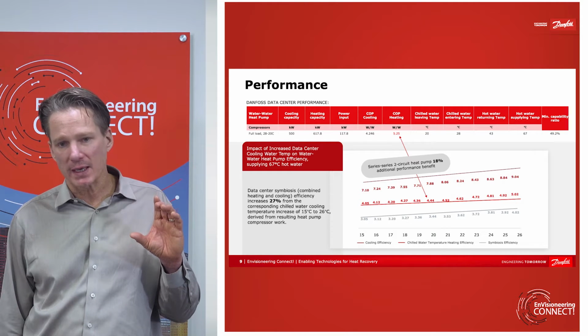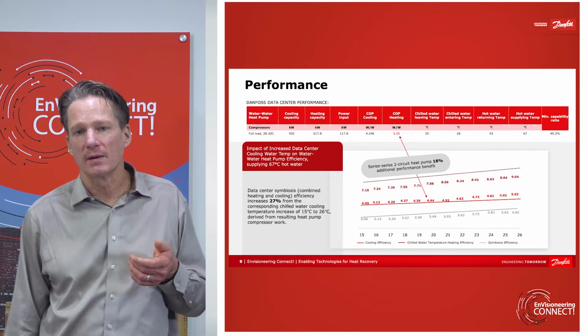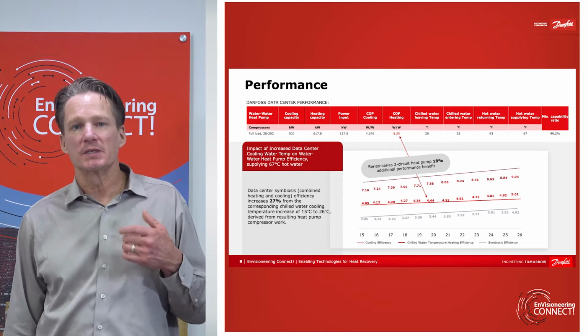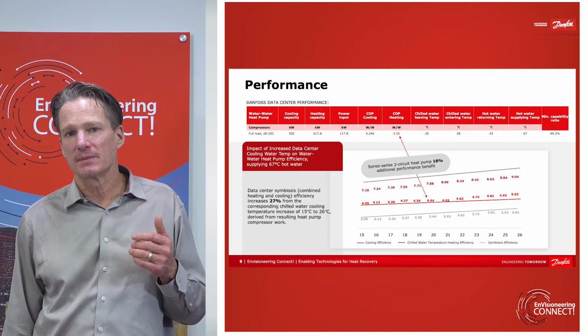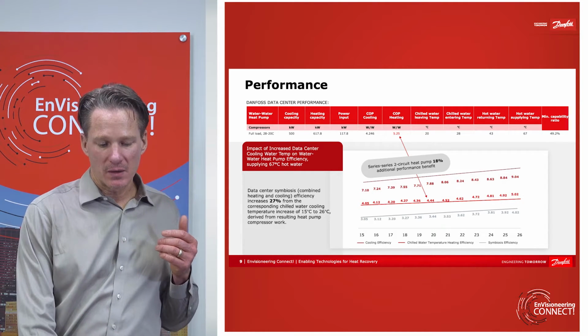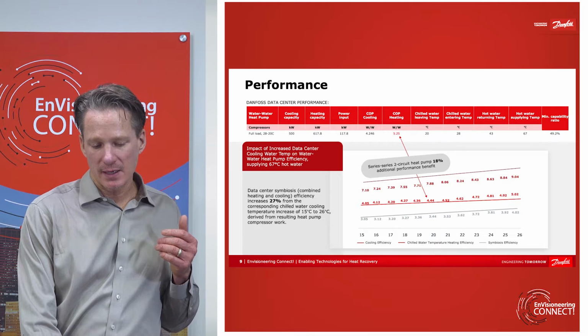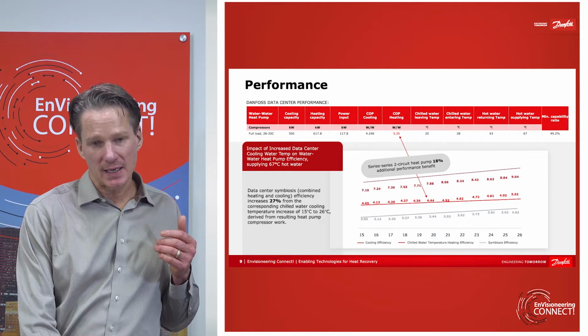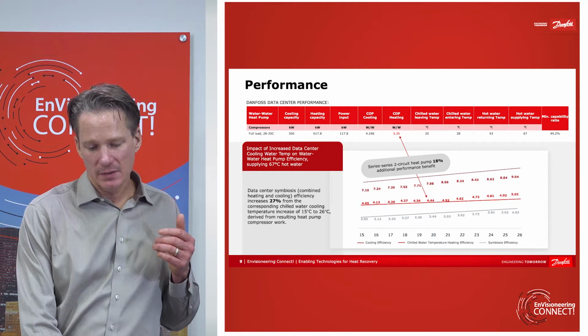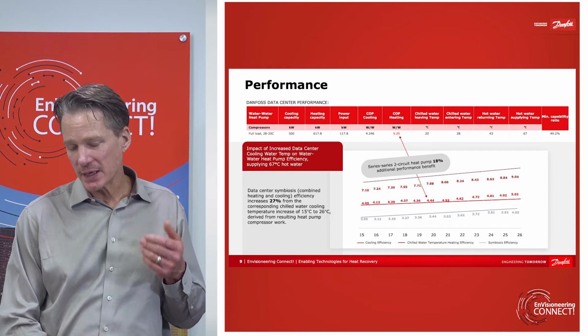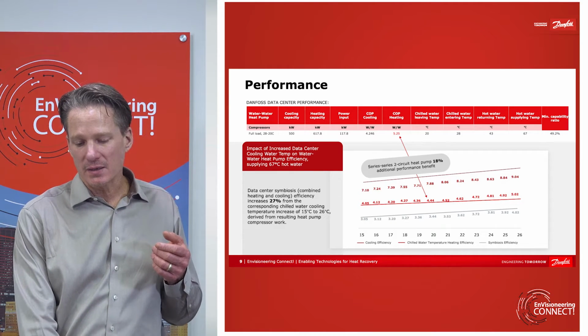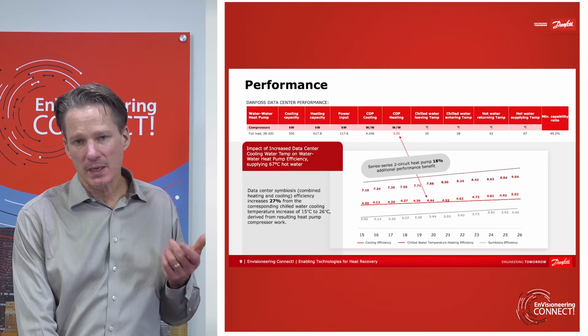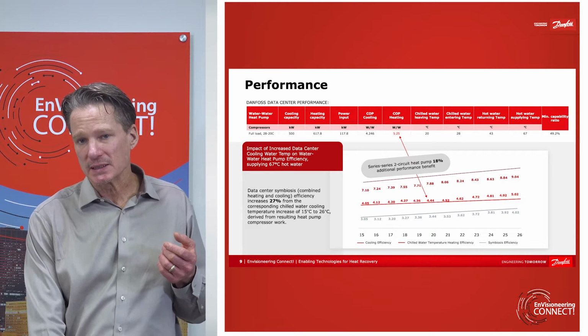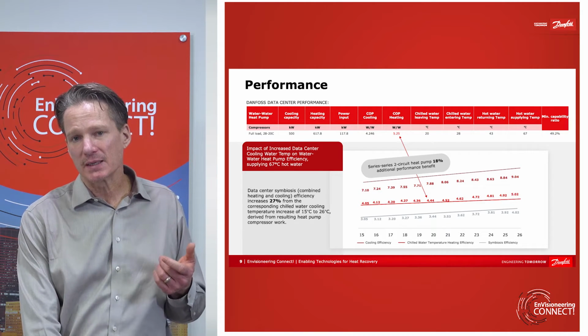And the reason for that is because you're requiring less work of the water-to-water heat pump to reject heat at the higher temperature. As you can see from here, also the efficiency of the heating that comes out on the high side, highlighted in red, goes up. And then another takeaway, the combined cooling and heating efficiency, or what we call the symbiosis efficiency, increases as well. That's the other factor that comes into play.